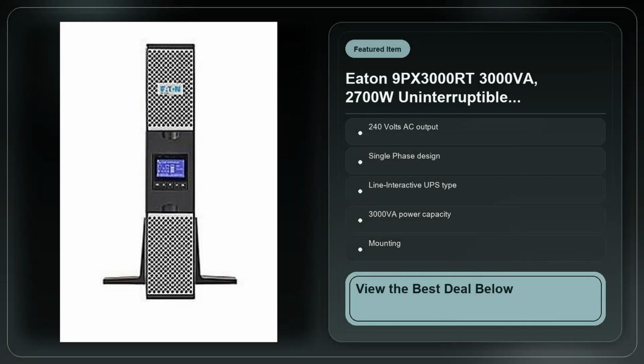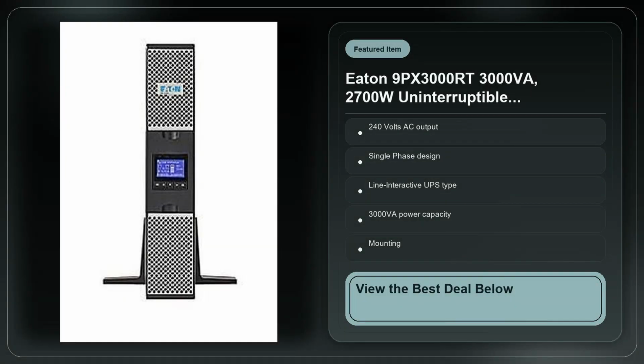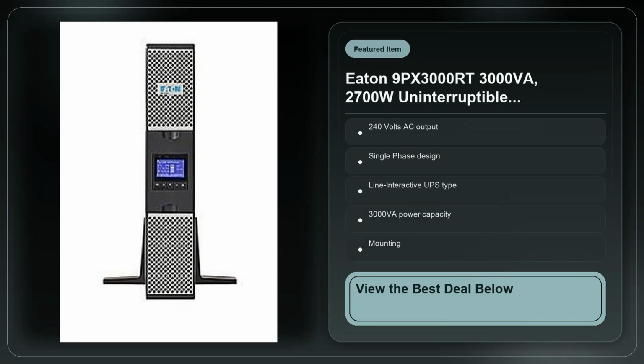One of the hidden trade-offs I discovered is the battery life expectancy. Like any sealed lead-acid battery, the internal packs will lose capacity over time, especially if you run the unit close to full load on a regular basis. Eaton recommends a battery replacement every 3 to 5 years, which is a cost you have to factor into the total ownership.